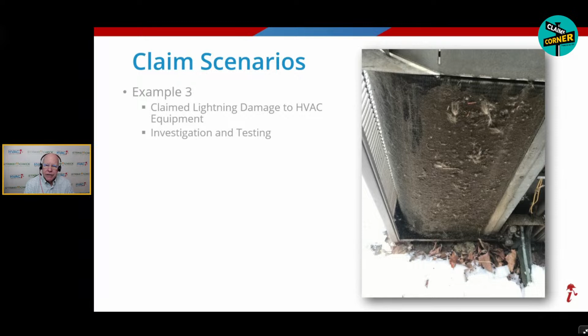Guess what? That compressor, when we tested it, shorted to ground, which means there was something going on, right? In this particular case, we deem that as wear and tear. It wasn't lightning. There was no lightning data. There was no surge. There was no other evidence of any other electrical event, but the compressor had seized up and failed because of the dirty coils. Liquid slugging. It was trying to work, but the coil was so dirty it couldn't. And over time, it just failed. So that happens all the time.